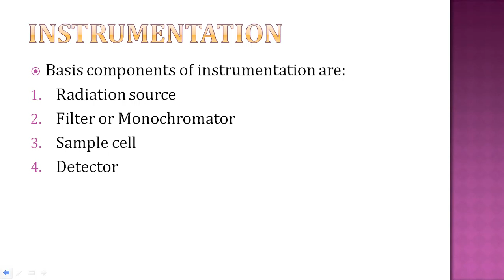Mercury vapor lamp at high pressure, means at 8 atmospheres, gives intense lines on a continuous background above 350 nanometer. Lines are seen at 365, 405, 436, 546, 579, 690 and 734 nanometer. Low pressure mercury vapor gives an additional line at 254 nanometer, and this mercury vapor lamp is used as a source in filter type of fluorimeters.